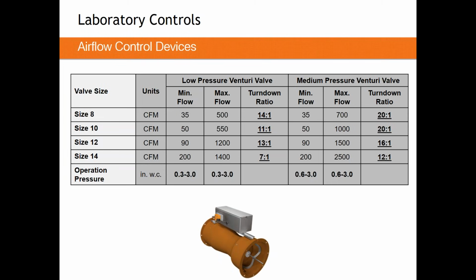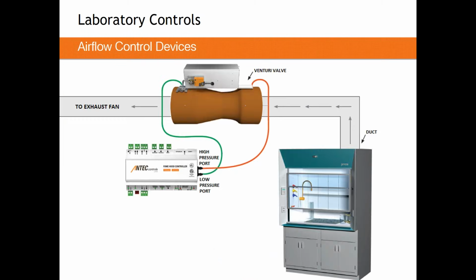Now, when I say that about the Venturi valve, that we have to have that pressure between 0.6 and 3, it's extremely critical. It's so critical that we put a transducer on every single controller we manufacture to measure that pressure drop. Because if you don't have it, the only fix is to go get it. If you only have 0.5 inches, your balancing team says these valves just aren't working, there's no fix within the valve and controls for that. You need to get more pressure to that system.